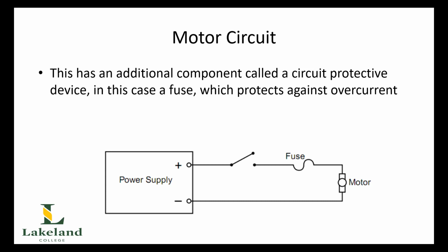Now motors are notorious for this if they are not being started up on VFDs or with some other type of soft start. We'll get into VFDs or variable frequency drives much later. Now the idea here of a motor overload is to allow that excess current, which can be as high as 6 to 10 times the current rating at startup, to not trip the system. And then once the system has settled down, i.e. the motor is at rotational speed, the fuse will then protect it from any further surges in overcurrent. Induction motors are notorious for this, and we'll talk about this in the actual chapter that discusses electrical motors.